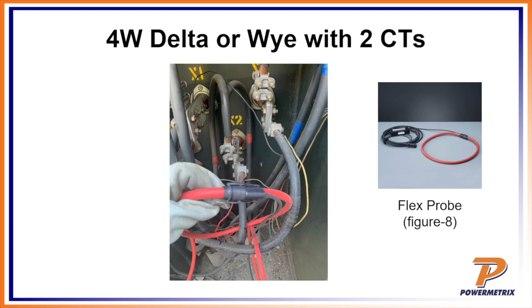What's great about the Powermetrix equipment is it actually shows this on that color diagram. We show a color diagram before we test the meter, and before we test the CTs. Before it tests the CTs, it will show you how to make those connections with these probes, and it will literally show you a figure 8 like this.